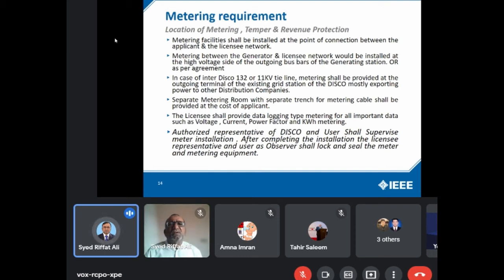And for the purpose of tamper and revenue protection and foreseeing future disputes between the seller and buyer, the authorized representative of the DISCO and the user shall supervise the meter installation. After completing the installation, the licensee representative and the user as observer shall lock the metering equipment in the room as well. So this last point is very important, and both sides should have trained and skilled persons to perform this kind of function and record all the observations at the spot as well.